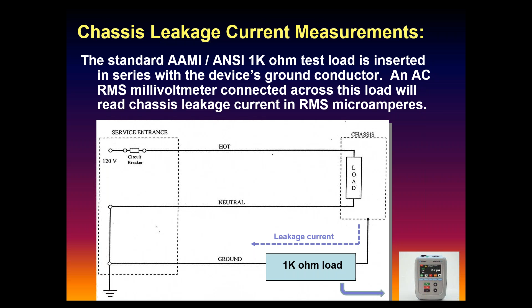So that's all we're doing with the safety analyzers. How does that come back - where does that source of leakage current come from? That's crucial going forward. Ultimately, before that leakage current can do any harm, we have to get it to the wrong place - once it can shock anybody.